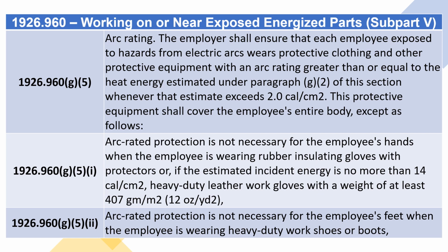1926.960(g)(5) Arc rating. The employer shall ensure that each employee exposed to hazards from electric arcs wears protective clothing and other protective equipment with an arc rating greater than or equal to the heat energy estimated under paragraph (g)(2) of this section whenever that estimate exceeds 2.0 calories per square centimeter. This protective equipment shall cover the employee's entire body, except as follows. (g)(5)(i) through (g)(5)(v).